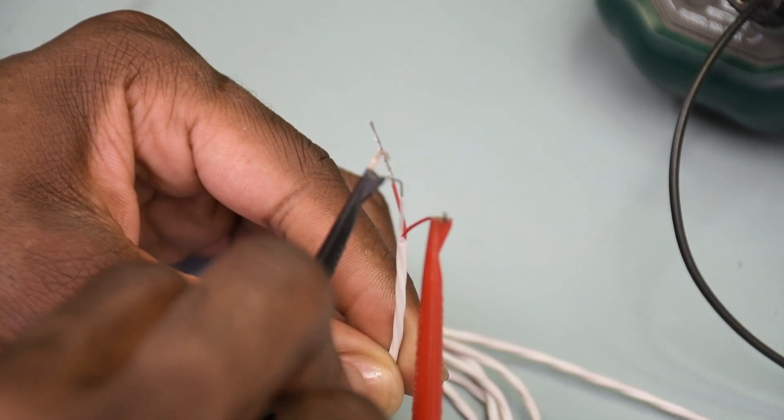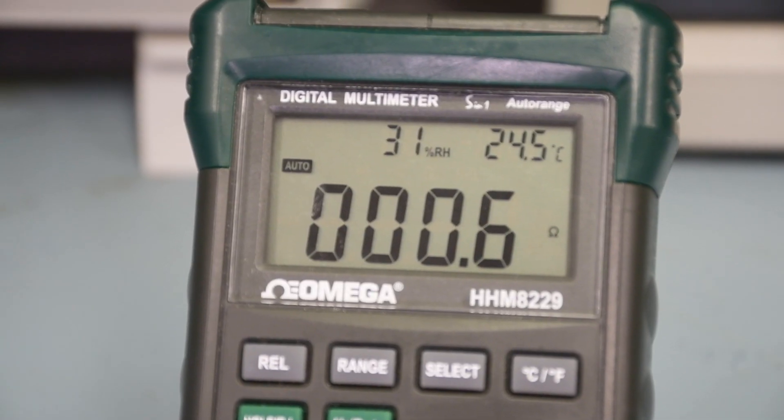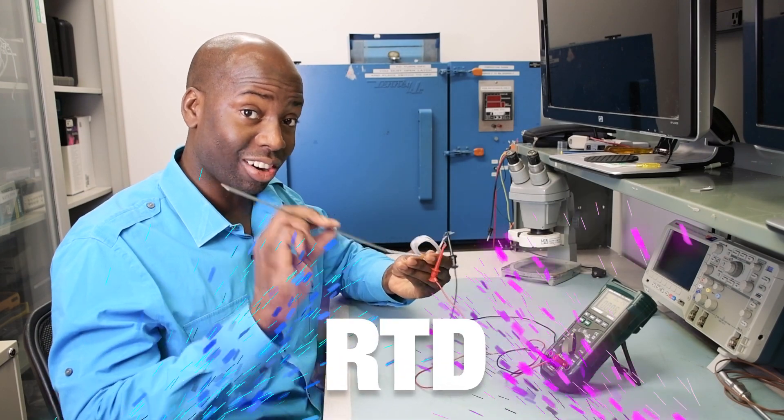Now, if this is an RTD, across one pair of wires, you're going to read a zero ohm resistance. So, I'm going to take my negative lead and move it over to the other wire, and I'm reading 0.6 ohms, which is pretty much next to zero. This is fair to say, this is a three-wire RTD.